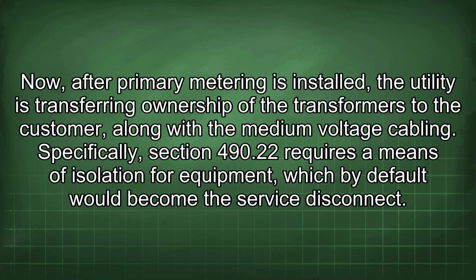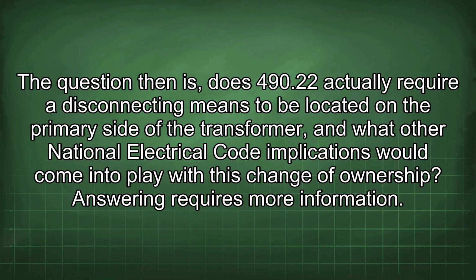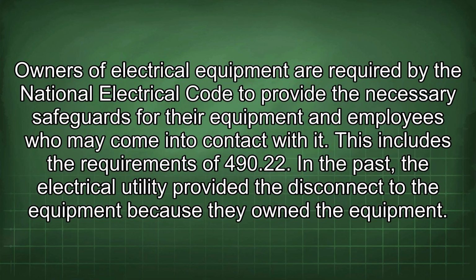service disconnect. The question then is, does 490.22 actually require a disconnecting means to be located on the primary side of the transformer? And what other National Electrical Code implications would come into play with this change of ownership? Answering requires more information. Owners of electrical equipment are required by the National Electrical Code to provide the necessary safeguards for their equipment and employees who may come into contact with it.